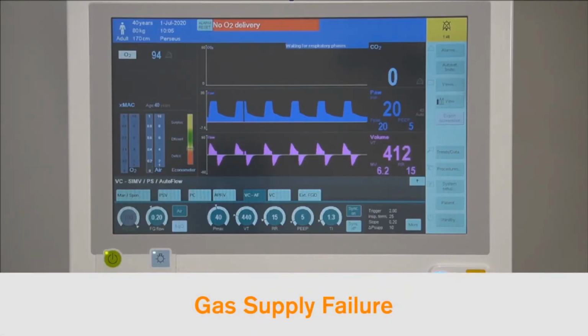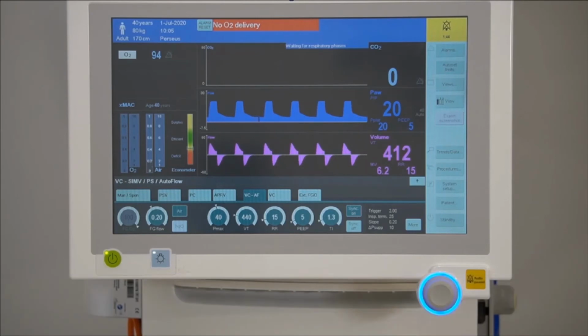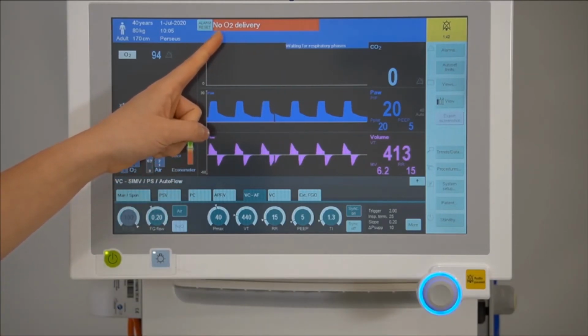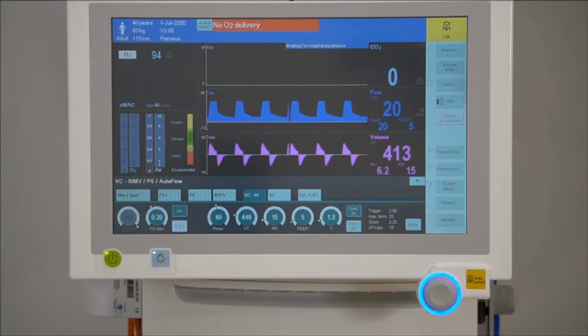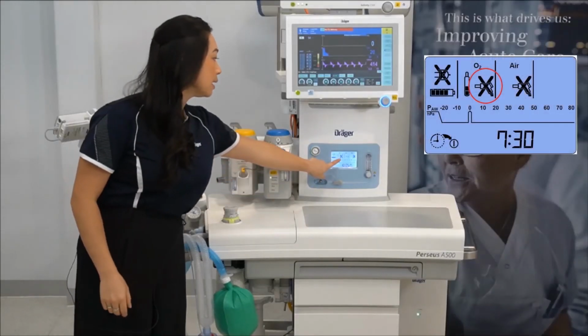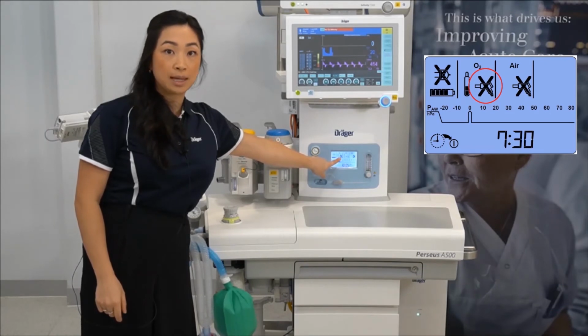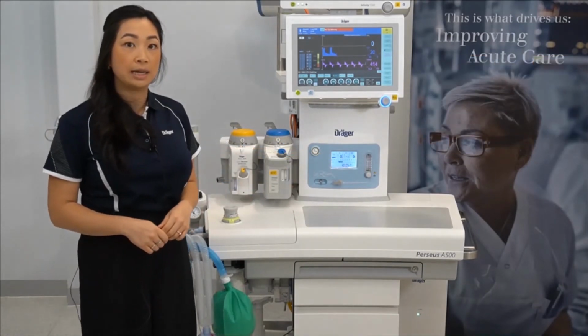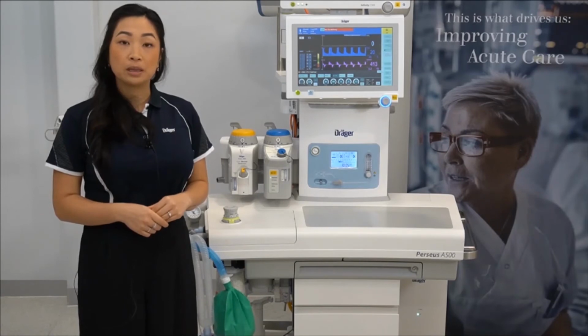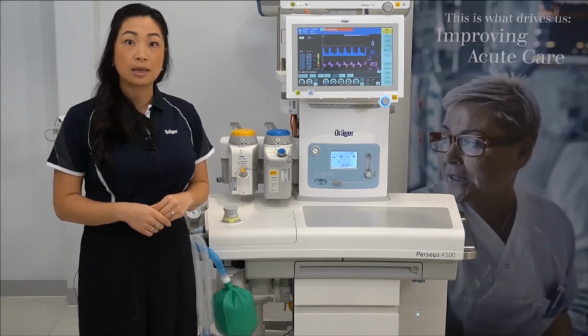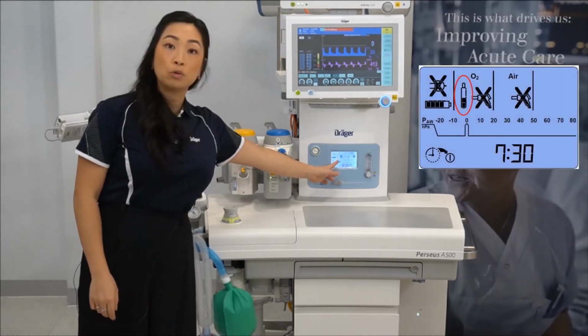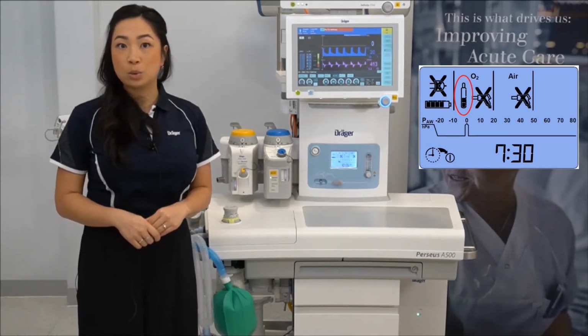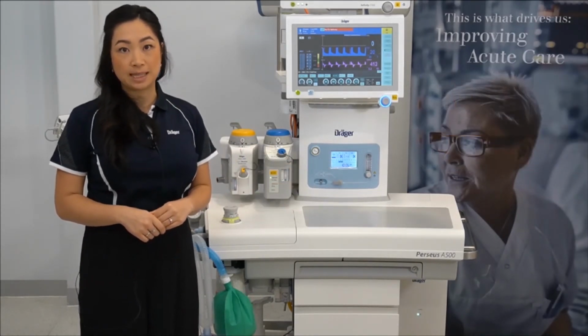In the event of a central gas supply failure, you'll see a high priority message being displayed. This will then prompt the user to open the corresponding reserve gas cylinder on the back of the device. You'll also notice a cross symbol through the central gas supply icon on the mixer screen. And when you open the reserve gas cylinder, the capacity of that cylinder will be displayed with every square representing about 25% capacity.